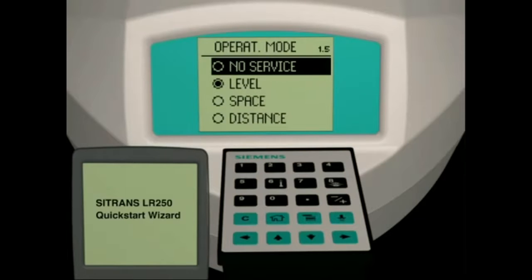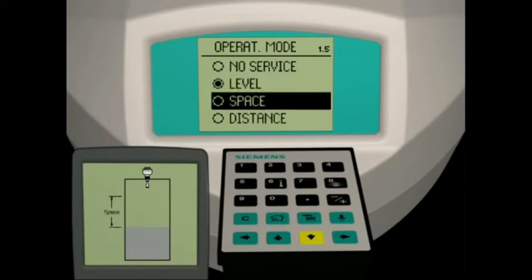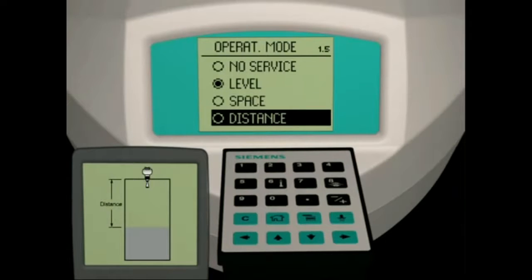The no service mode is used to remove the unit from active service. The level mode is used to indicate the level of material referenced from the low calibration point — also referred to as the height of the material in the vessel. The space mode indicates the distance from the high calibration point to the material level. The distance mode indicates the distance from the sensor reference point to the material level.